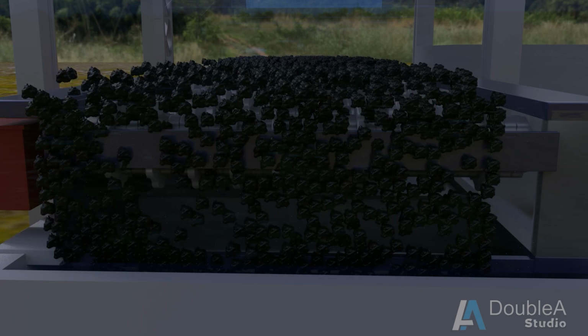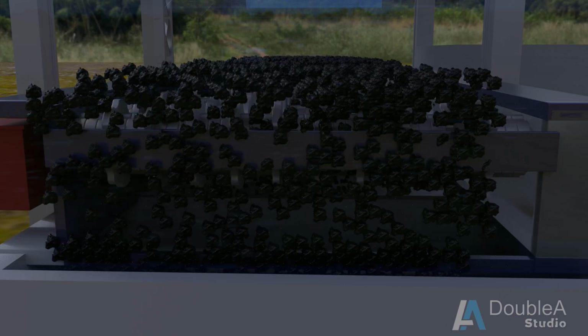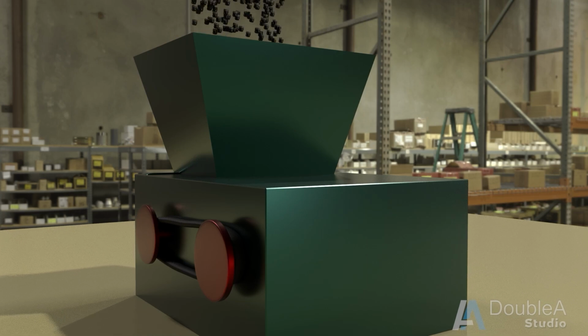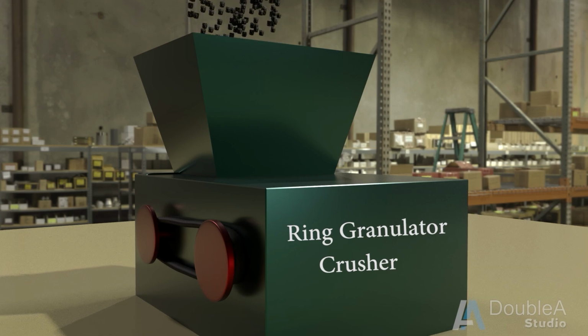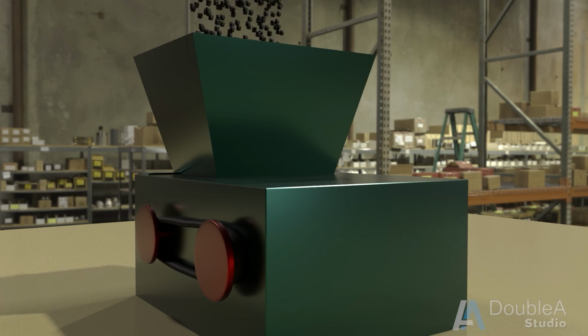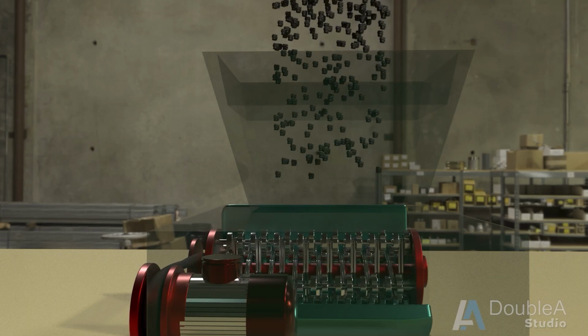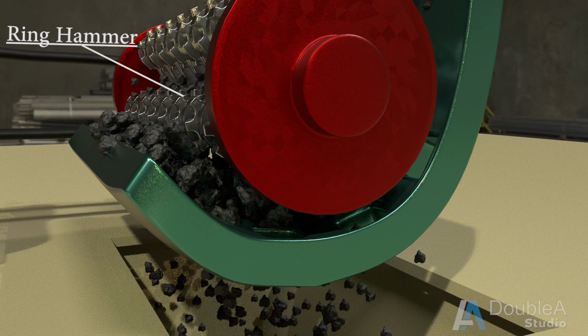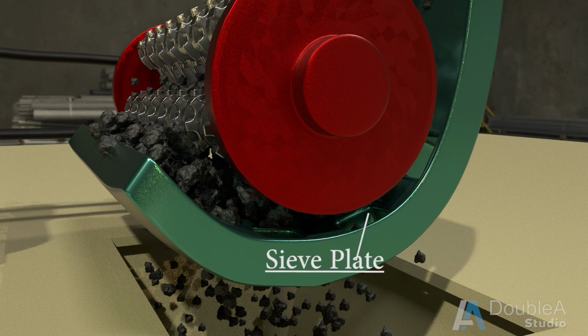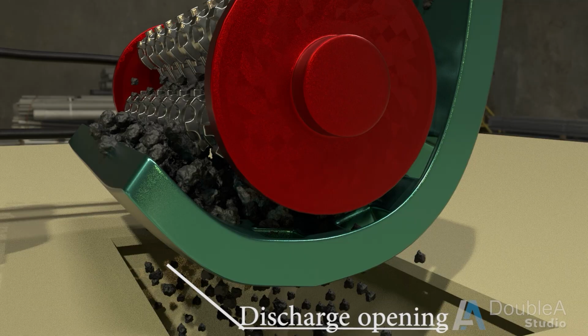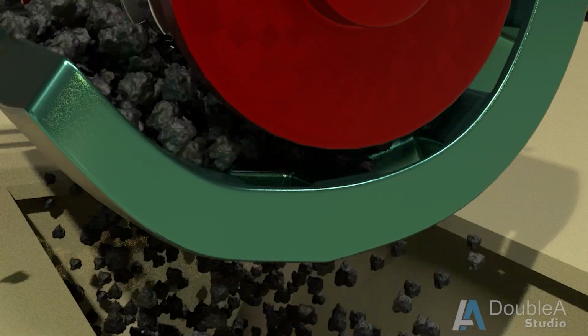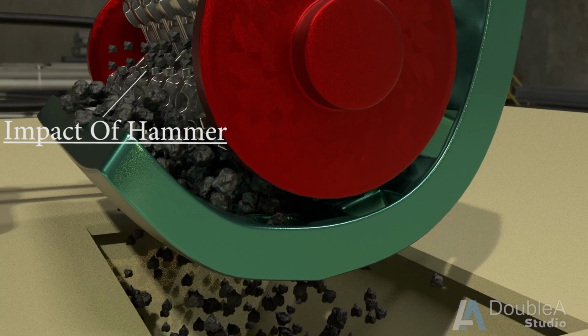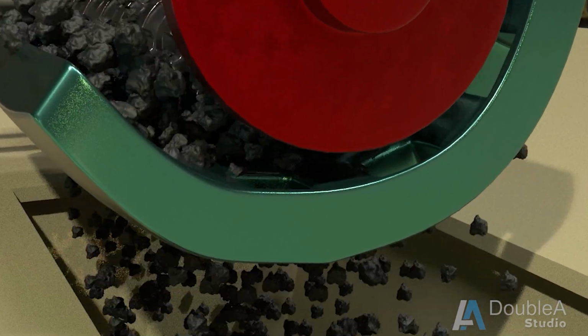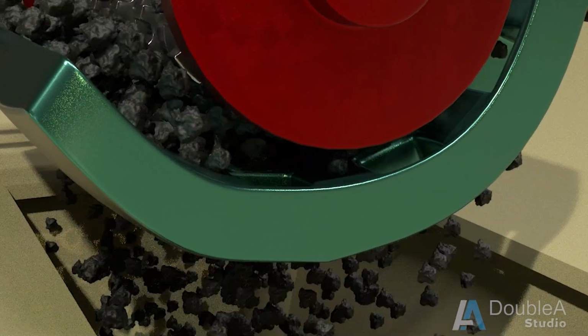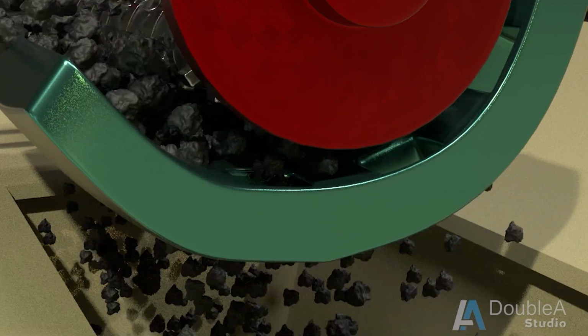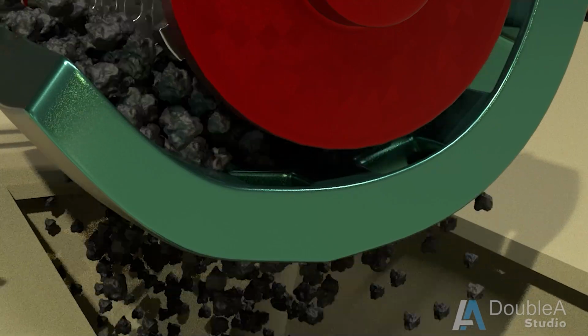We can see that the coarse coal flows down the chute of roller screen and is fed to the mouth of the crusher. This type of crusher is called ring granulator crusher. Such machines are fabricated from heavy steel plates and are specially designed for continuous crushing of coal. It mainly consists of rotor shaft, ring hammer, crushing plate, sieve plate, and discharge opening. Crushing of coal takes place by two types of action. One is by the impact of ring hammers and other is by rolling compression between crushing plate and ring hammer. Crushing reduces size of coal up to 20 millimeters. These machines are ideal for crushing coal to a suitable size for pulverization.